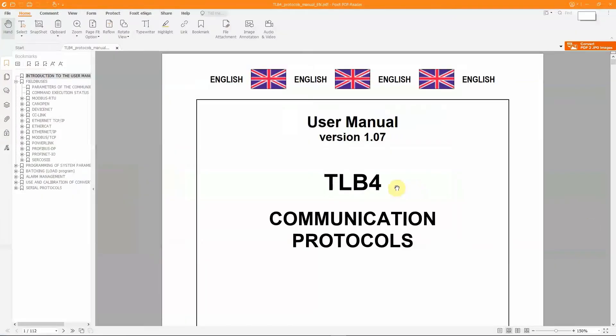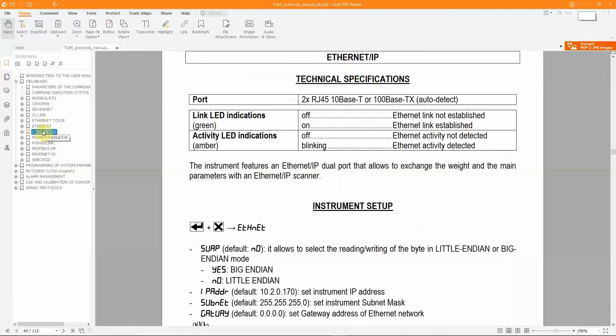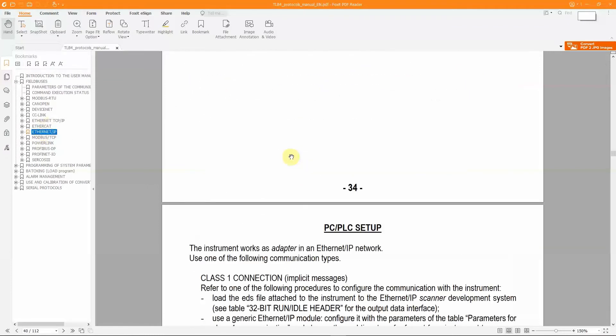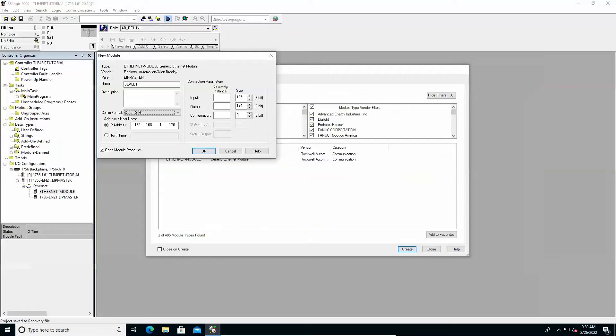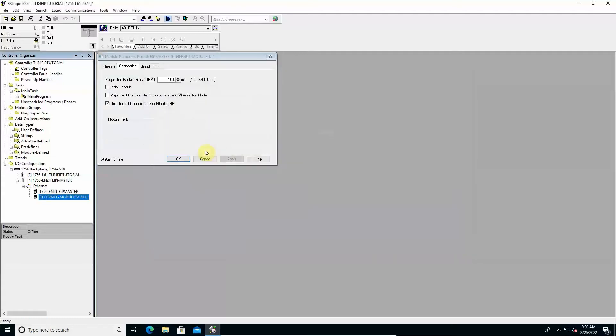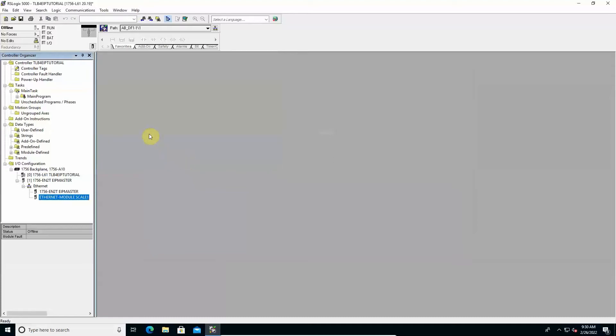Complete the fields in the connection parameters section using the information contained in the table parameters for class 1 communication in the protocols manual with reference to the pure data column. Input assembly instance 101 and size equal to 22. Output assembly instance 100 and size equal to 8. Configuration assembly instance 128 and size to 0. Click OK to complete the configuration and return to the main window.